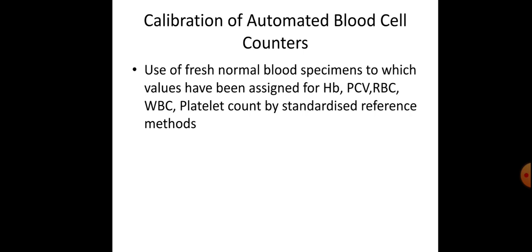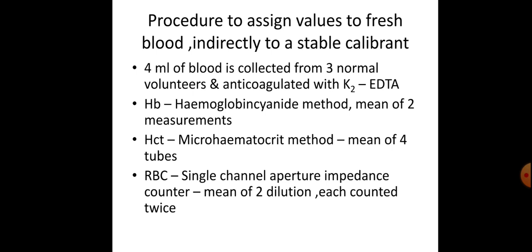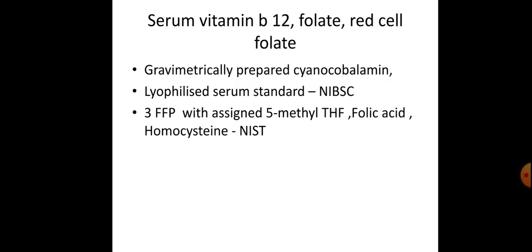Calibration of automated blood cell counters: use fresh normal blood specimens to which values have been assigned for hemoglobin, packed cell volume, red blood cell count, white blood cell count, and platelet count by standardized reference methods. Procedure to assign values to fresh blood indirectly to a stable calibrant: 4 ml of blood is collected from 3 normal volunteers and anticoagulated with K2EDTA. For hemoglobin, the hemiglobincyanide method is used, taking the mean of two measurements. Hematocrit is measured by the microhematocrit method, taking the mean of 4 tubes. For RBC, a single channel aperture impedance counter is used, taking the mean of 2 dilutions, each counted twice.